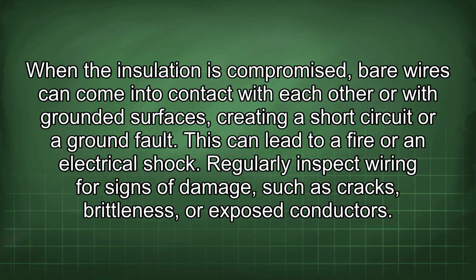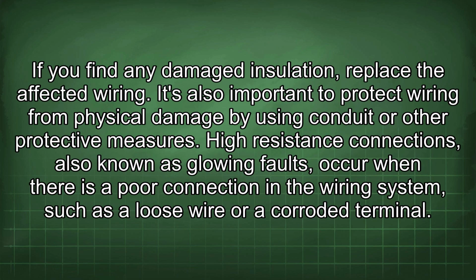Regularly inspect wiring for signs of damage, such as cracks, brittleness, or exposed conductors. If you find any damaged insulation, replace the affected wiring. It's also important to protect wiring from physical damage by using conduit or other protective measures.